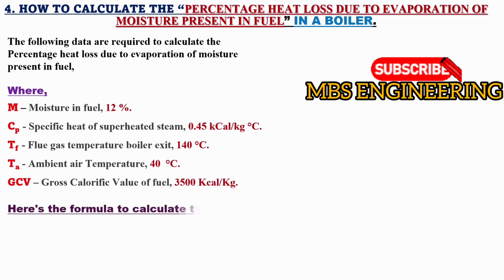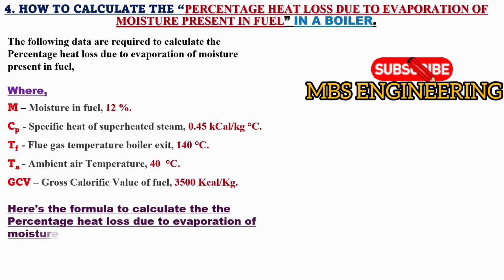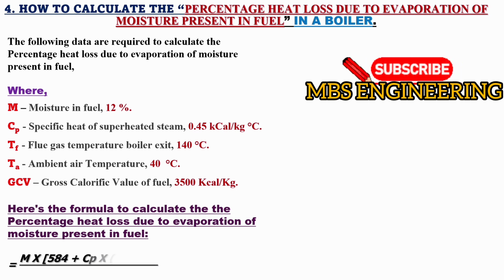Here's the formula to calculate the percentage heat loss due to evaporation of moisture present in fuel in a boiler: M multiplied by (584 plus Cp) multiplied by (Tf minus Ta), and then the obtained value is divided by GCV.